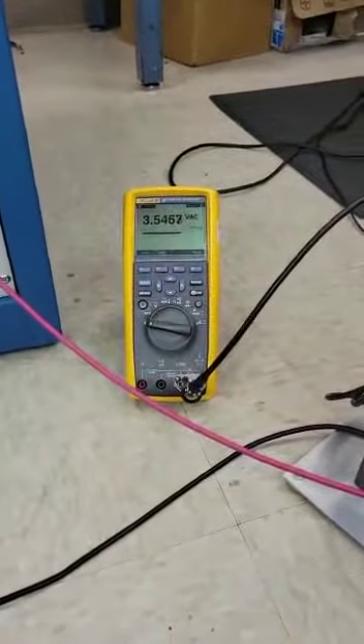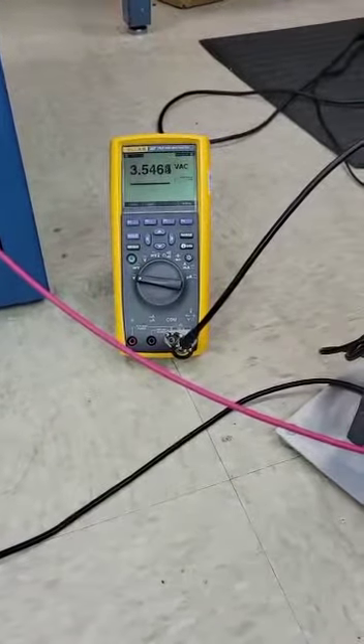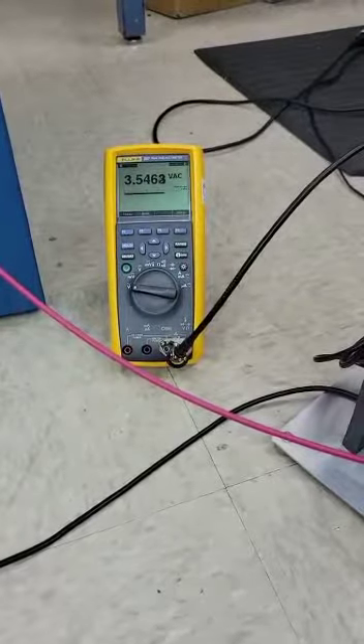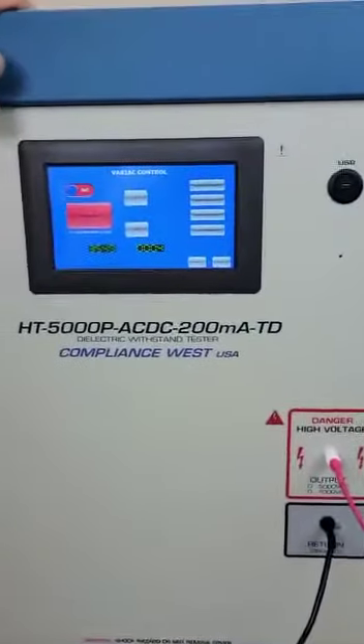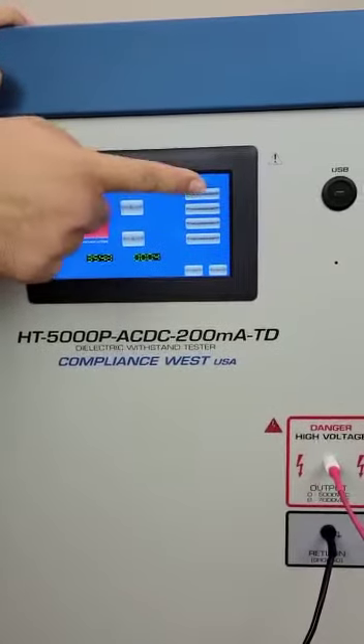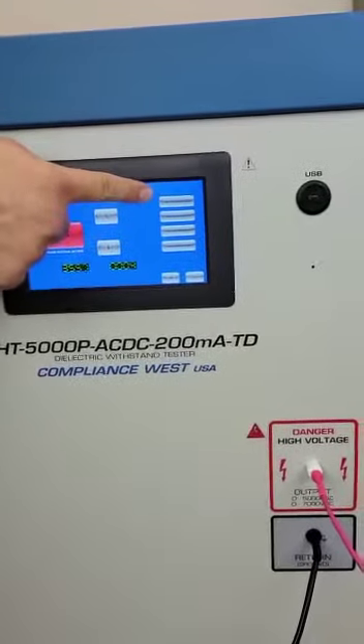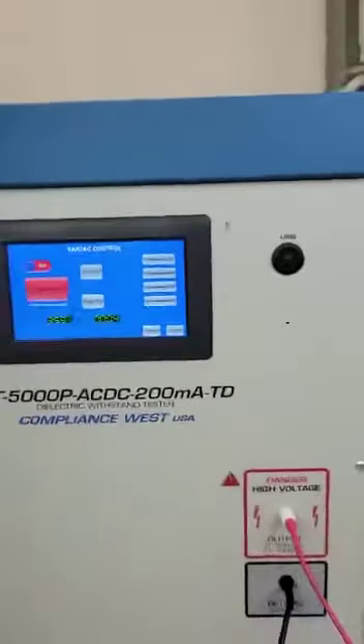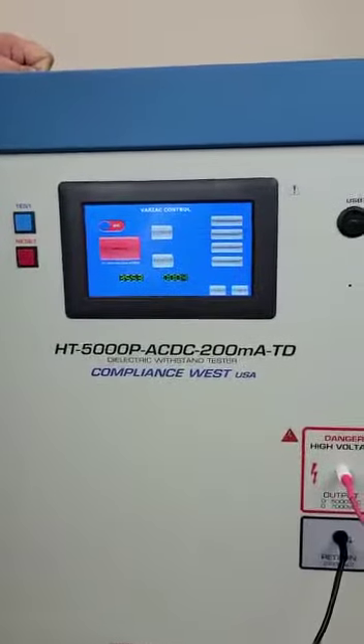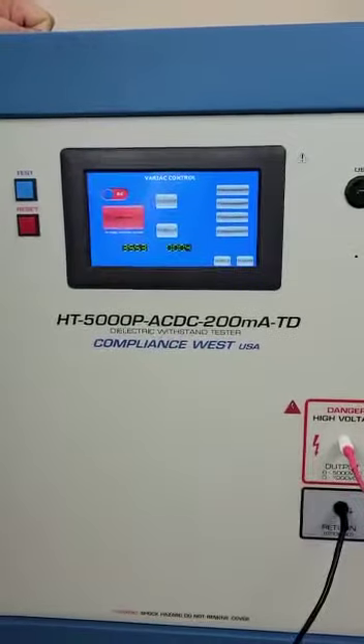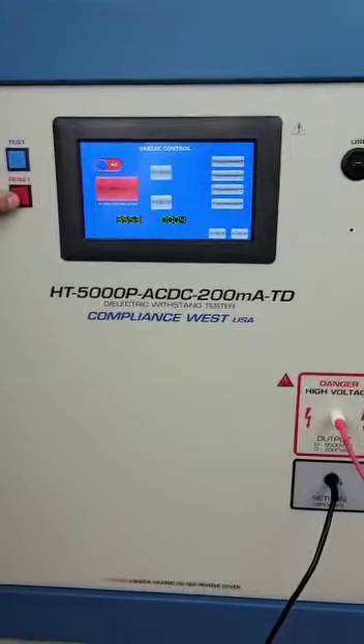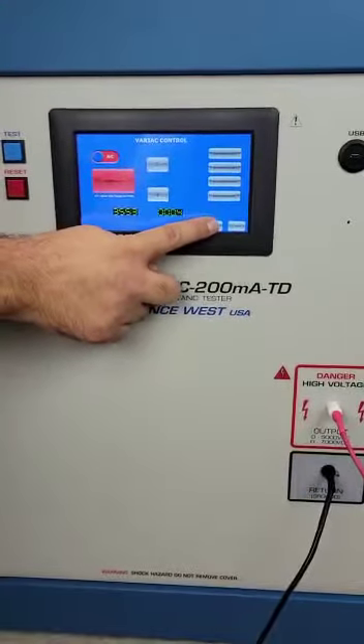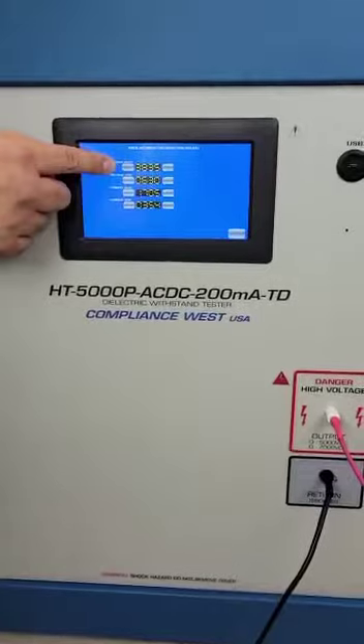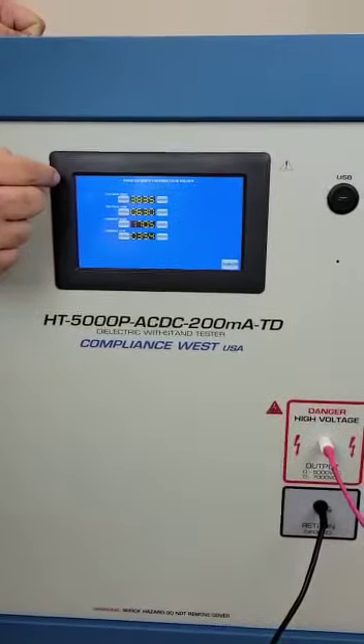Once we're there, we take note of the reading on the multimeter, 3546. The next step is to press cal voltage high, which is the first one. Once we do that, we can release the test button. We go back to the previous screens. Once we hear the Variac go to 0, we go back, and we can enter the value of the multimeter in the first line.